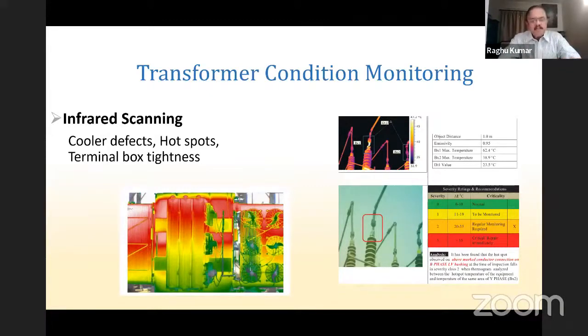This identifies cooler defects. It has been detected after years that certain coolers were not opened, which affects the cooling efficiency. This can be detected only with thermal imaging. And certain other hotspot issues can also be identified with this infrared scan.